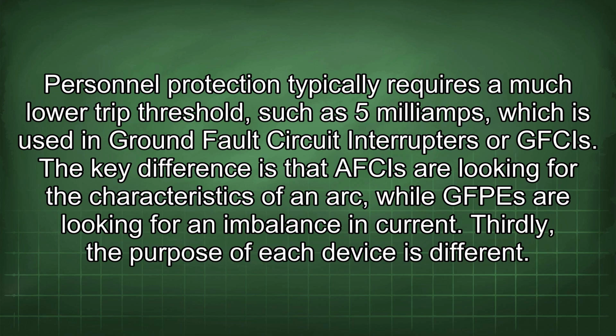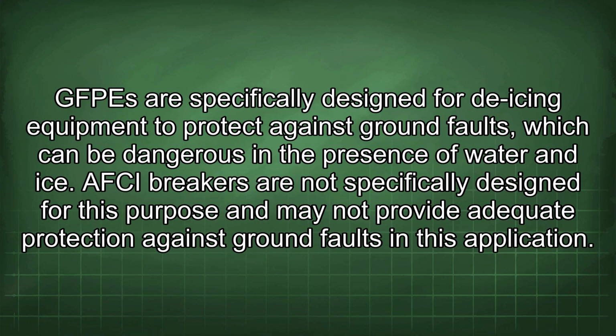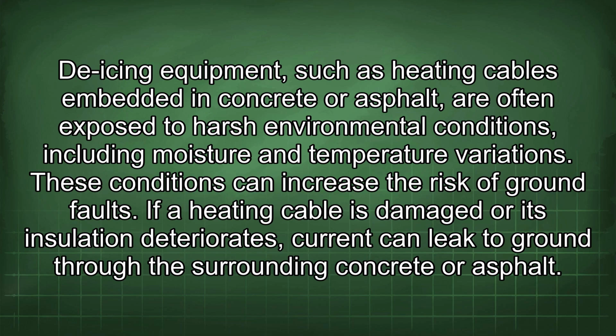Thirdly, the purpose of each device is different. GFPEs are specifically designed for de-icing equipment to protect against ground faults, which can be dangerous in the presence of water and ice. AFCI breakers are not specifically designed for this purpose and may not provide adequate protection against ground faults in this application. De-icing equipment, such as heating cables embedded in concrete or asphalt, are often exposed to harsh environmental conditions, including moisture and temperature variations. These conditions can increase the risk of ground faults.